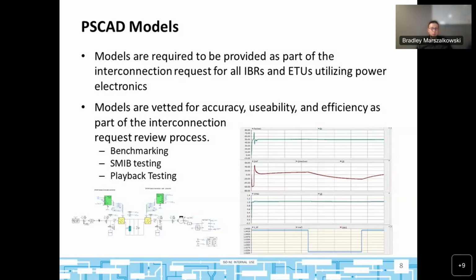We also require a report showing a benchmarking analysis between the PSCAD model and the PSS/E model submitted with the interconnection request. This is because we want to make sure the PSS/E model is also as accurate as possible. We put a lot more faith in the PSCAD models than the PSS/E models, since more emphasis is put on the PSCAD models, so we try to line up the PSS/E model with that PSCAD model within reason. There are limitations to this, again, because of everything discussed earlier in the presentation.